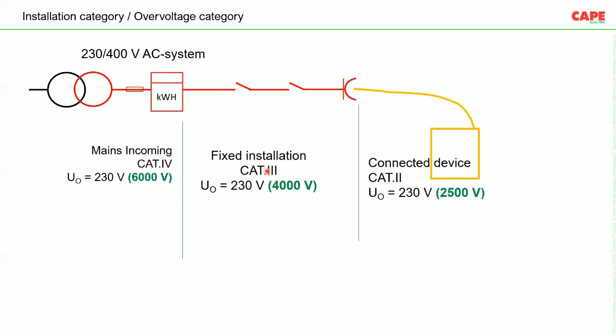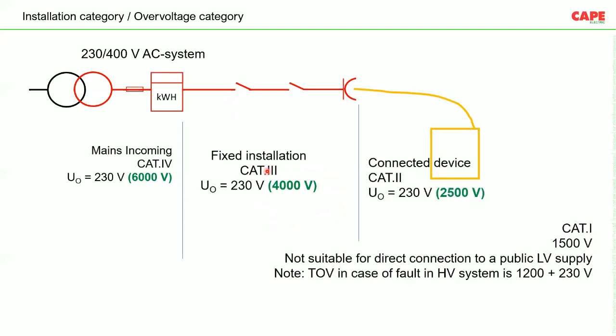So these are the categorizations, for example. Now, a category 1 device is an electronic appliance which can handle up to 1500 volt transient overvoltage. But please note that these devices are not suitable for direct connection to a public LV supply. If you are using electricity from the electricity supplier's facility, then of course a class 1 or category 1 device, we are not supposed to connect directly to the electricity supply.